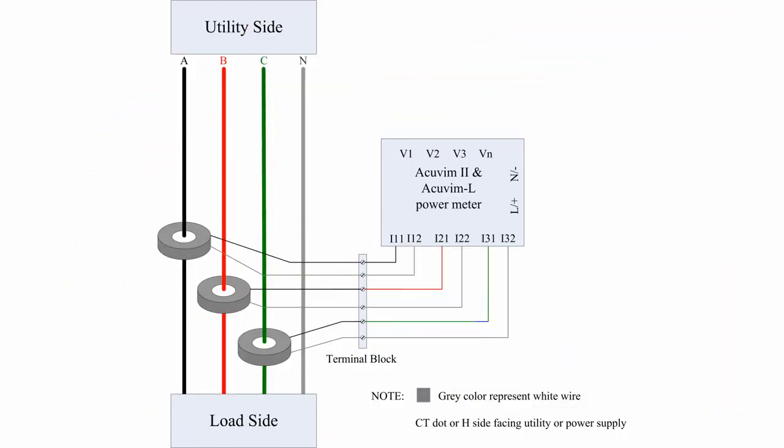Next, the voltage of each phase needs to be wired into the Acuvim II power meter. The black line connects phase A to the V1 voltage input terminal on the meter. The same principle applies to phase B and C. The neutral line is connected to the VN terminal.